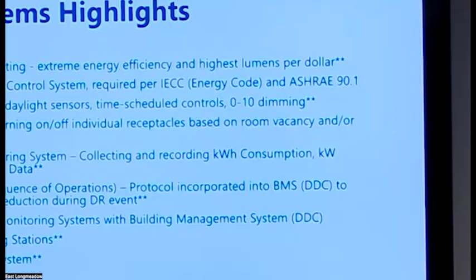Perfect. So, hi. Since this is the first introduction of the electrical systems, I'll go high level on what systems we're suggesting to implement in our design. And of course, we're implementing LED interior and exterior lighting, which is expected to bring you extreme energy efficiency and high lumens per dollar. What we're also bringing into the design is the wireless network lighting control system, which is required by IECC, the international energy code, and also ASHRAE. Also, we're putting in occupancy, vacancy sensors, daylight sensors, time schedule controls, and 0-10 dimming for lighting.